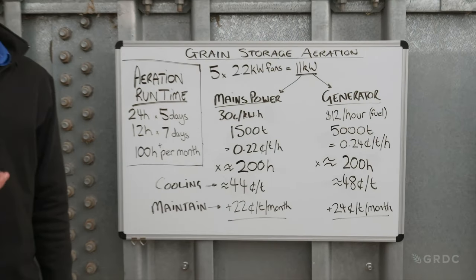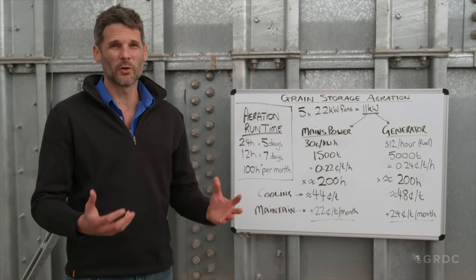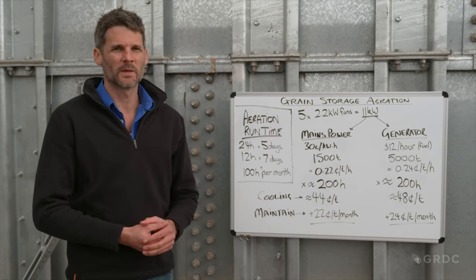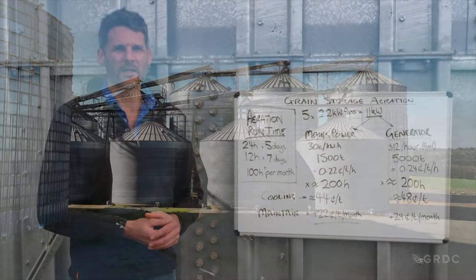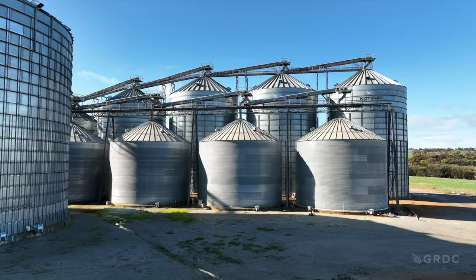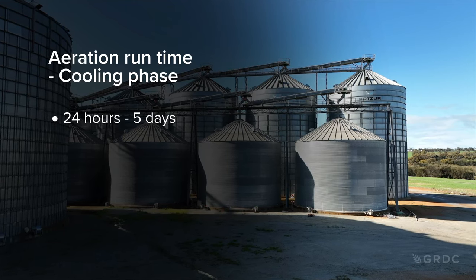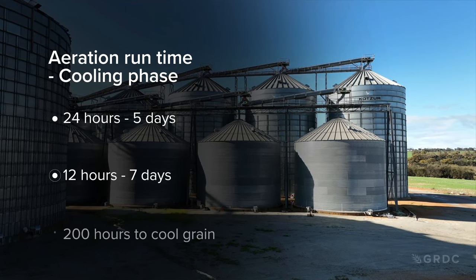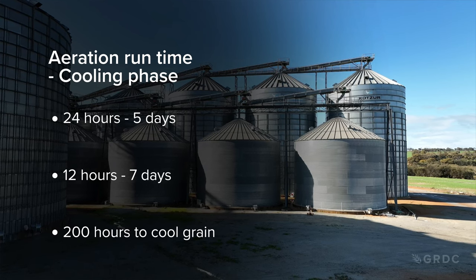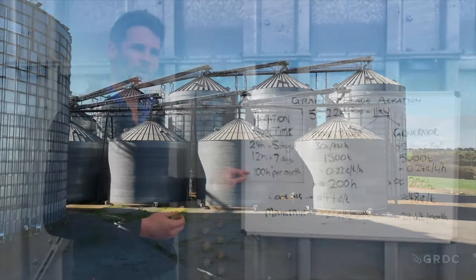When calculating the cost of running aeration cooling fans, the first thing to work out is how long the fans will actually run for. Controllers will typically do a cooling phase and then a maintenance phase. In the cooling phase, they'll run fans for 24 hours for the first five days, 12 hours for the next seven days — so about 200 hours. From then on, they'll run the fans for about 100 hours a month for maintenance mode.